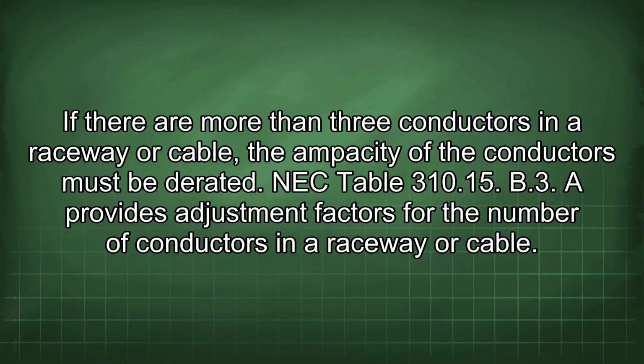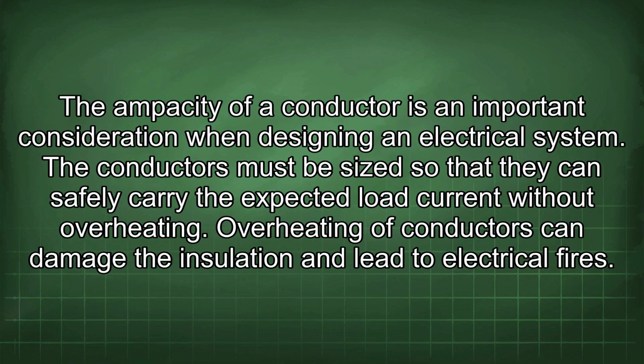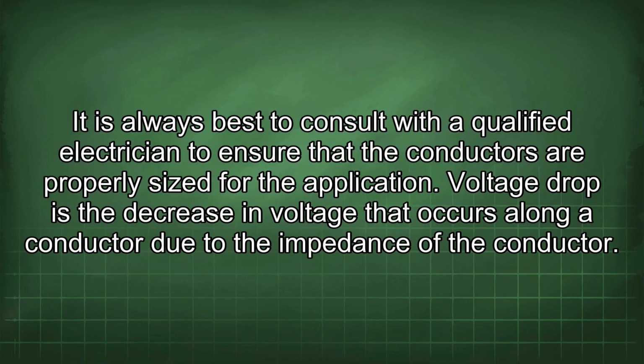If there are more than 3 conductors in a raceway or cable, the ampacity of the conductors must be derated. NEC Table 310.15(B)(3) provides adjustment factors for the number of conductors in a raceway or cable. The ampacity of a conductor is an important consideration when designing an electrical system. The conductors must be sized so that they can safely carry the expected load current without overheating. Overheating of conductors can damage the insulation and lead to electrical fires.